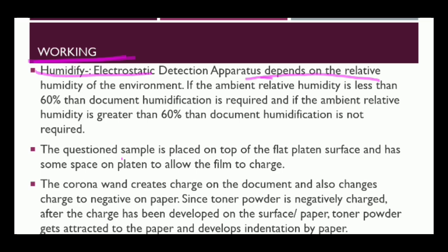First of all, we should make sure that the document is properly humidified, and this can be done using a humidification chamber. Then the questioned document will be placed on the platen surface, and there should be minimal wrinkles and distortions because it will make the examination easy. Then cover it with the charging film. Make sure that the charging film covers the document completely and makes full contact with the platen surface.